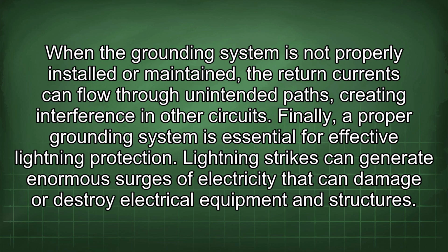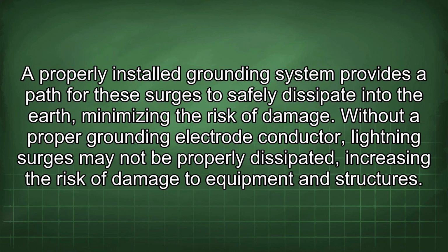Finally, a proper grounding system is essential for effective lightning protection. Lightning strikes can generate enormous surges of electricity that can damage or destroy electrical equipment and structures. A properly installed grounding system provides a path for these surges to safely dissipate into the earth, minimizing the risk of damage. Without a proper grounding electrode conductor, lightning surges may not be properly dissipated, increasing the risk of damage to equipment and structures.